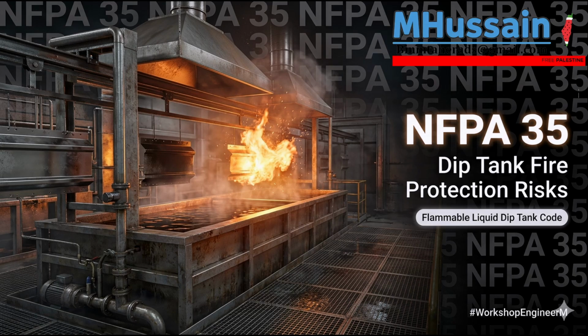But many highly refined solvents like toluene or xylene are excellent insulators. They have virtually zero conductivity. Right. And if you dump charged powder into an insulating liquid, the static charge just sits on the surface of the liquid, accumulating until it arcs to the metal wall. So what's the solution? If you are using a low conductivity liquid, the standard mandates you must engineer an alternative solution. You either have to completely inert the internal vapor space of the tank with nitrogen gas, so even if a spark arcs, there is no oxygen to burn, or you must use specialized anti-static additives to artificially boost the liquid's conductivity above 50 picosiemens per meter, assuming there's no second phase like water present.